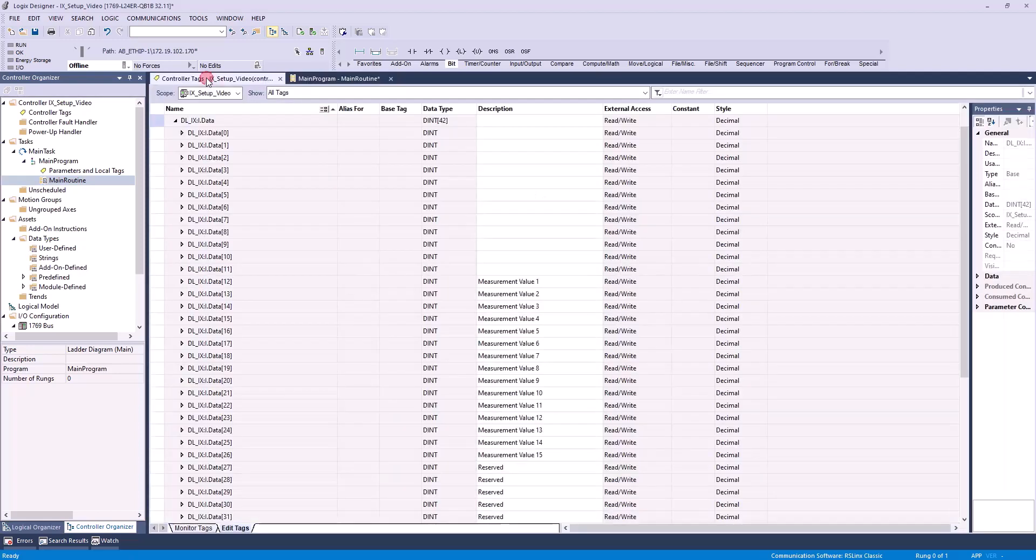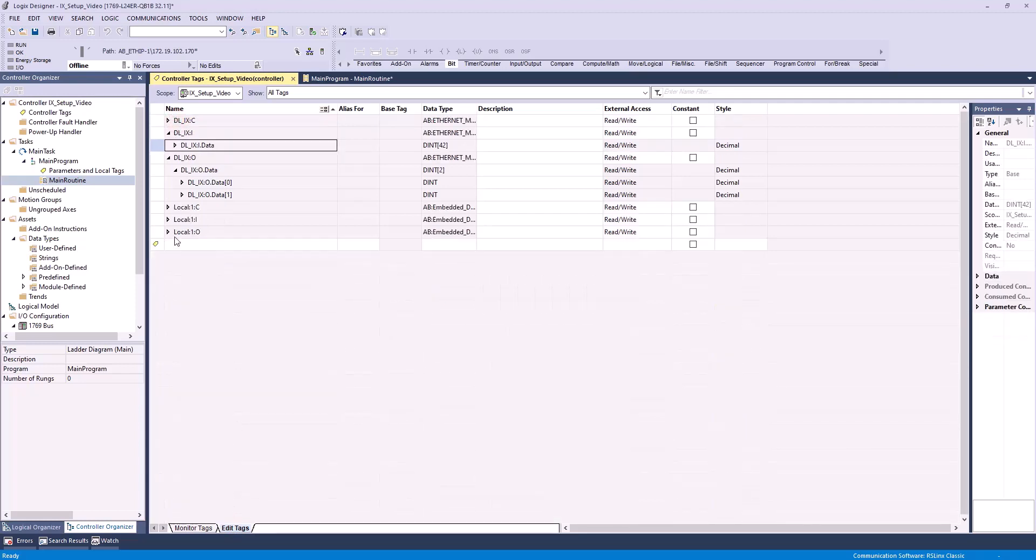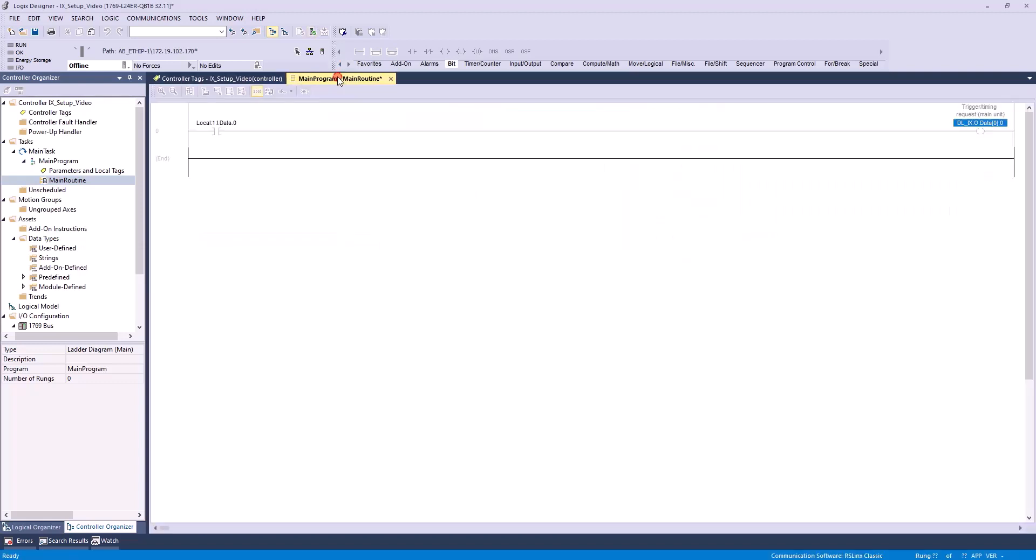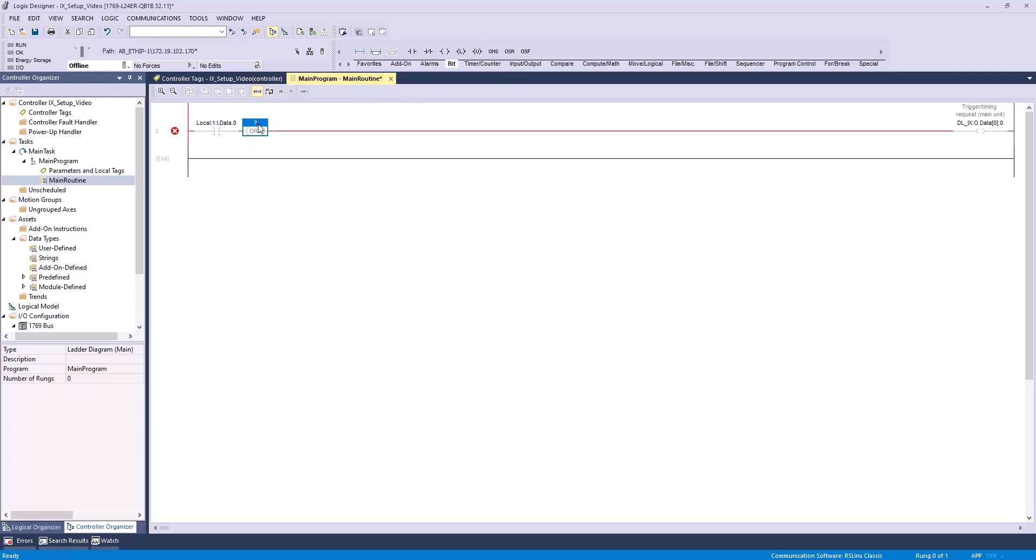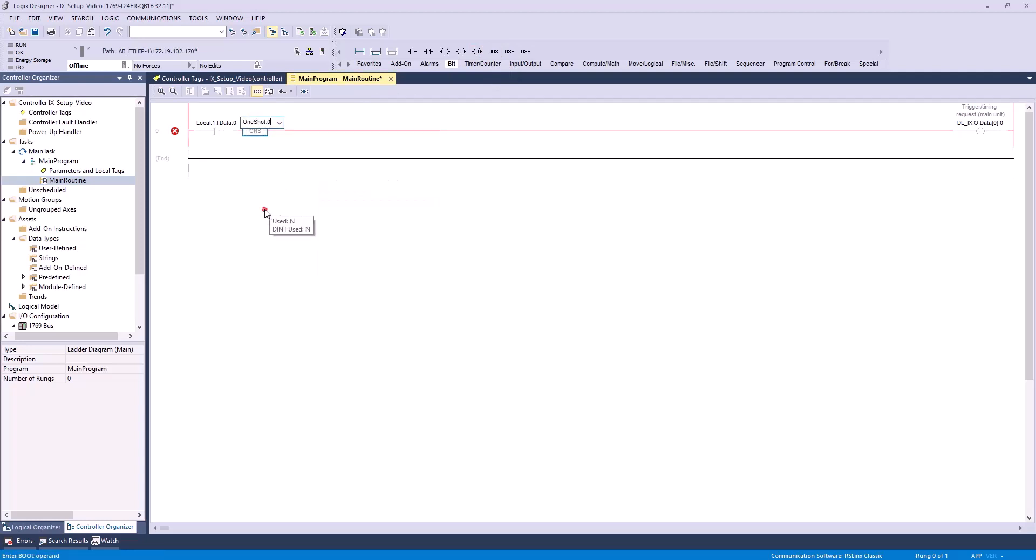Now, before we add our next element, we'll want to get back to our controller tags, then click on the Edit Tags tab. Here, we'll add a tag called OneShot. We can leave it as a DINT type tag, as this is essentially a dummy bit used to define the next element of our ladder logic. Now I can go back to our main routine, and I'll drag this OneShot icon next to our normally open contact. I can now define it as OneShot0 thanks to the tag we created.